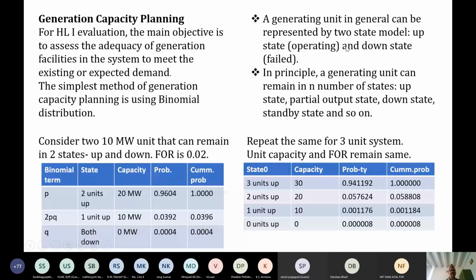In principle, a generating unit can remain in n number of states: up state, partial output state, down state, standby state, and so on. In partial output states, you can have multiple partial output states. So if a generator is rated for 100 megawatt, if it generates 95 megawatt, that is also a partial output state. If it generates 90 megawatt, that is also a partial output state. If it generates 10 megawatt, it is also a partial output state. So there can be n number of possible states for any generating station in principle. But usually we are concerned about the two-state model, whereby we represent a generating unit as either in up or operating state with full capacity, or in down or failed state with zero capacity.